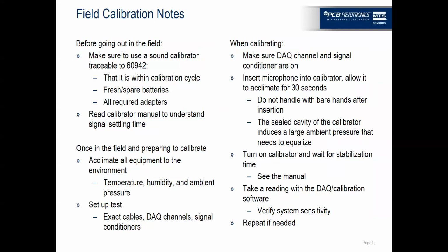Once the microphone has been inserted in the calibrator for 30 seconds, turn on the calibration and wait for the stabilization time. Again, see the manual for that. Take a reading with your DAQ or your calibration software and verify the overall system sensitivity. If it's a big change since the last time you did a measurement with this setup, check it again just to verify it, because your last time you did a test like this, you may have been testing in very cold temperatures and you may now be testing in very hot temperatures, and you may have 1/10 to 2/10 to 3/10 of a dB of change. And that's an important thing to take note of over the course of your measurement history.